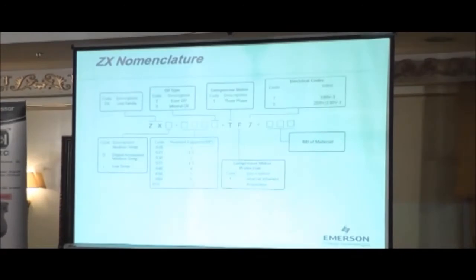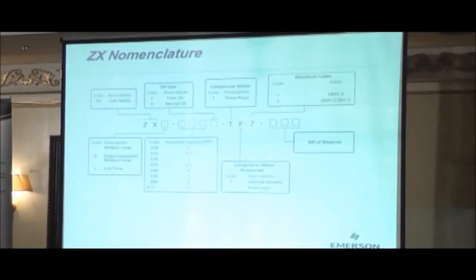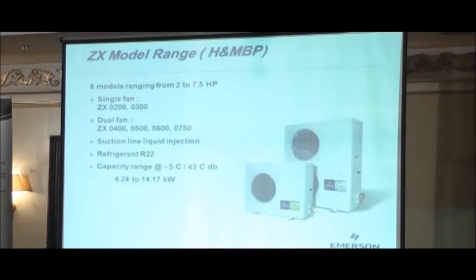Then we have the compressor motor, TF7. T is for three-phase, F means it's got internal protection, and the last digit indicates the voltage. So for Saudi Arabia, we're supplying 200 or 230 volt, that will be voltage code 5, so you'll get a TF5. And for 380 volt application, you get a TF7. The last three digits are the bill of materials. The bill of materials will tell you what is fitted in the unit. We have various options available, but Basuna has standardized on 2 bills of materials. I'll explain to you what is fitted in there.